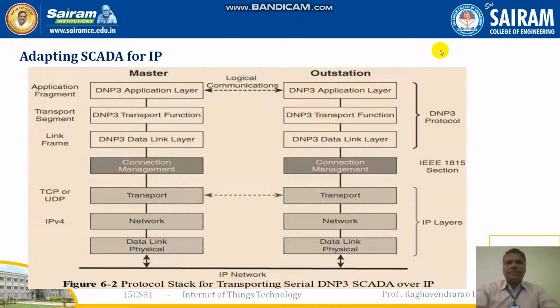The connection management links the DNP3 with the IP layers. You can see here, this is connection management, which links the IP layers as well as the DNP protocol. In addition to the configuration parameters and methods necessary for implementing the network connection, the master side initiates the connections by performing a TCP active open. The outstation listens for the connection request by performing a TCP passive open.